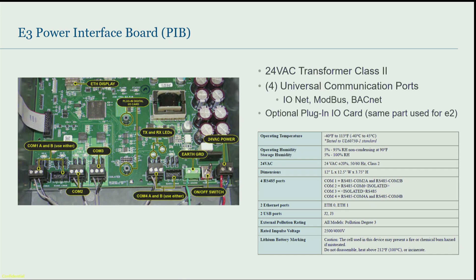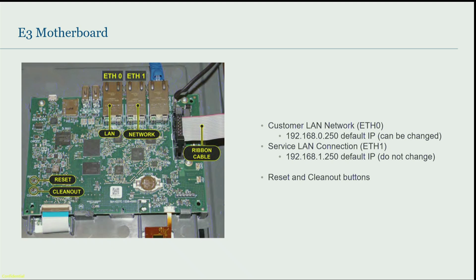This is on the back door. You open up the door. These are the Ethernet ports on the back door, like I said. Everything's web-based. So there's the default IPs for each Ethernet port, and you can change those if you need to in the controller. A lot of times we use Ethernet 0 as the building network or a cell network, whatever you may need to use to connect remotely into the store. And then Ethernet 1 is used for local connection like a display or your laptop if you have their service in the controller. Reset and clean out inside the door just like it had in the E2, same format.